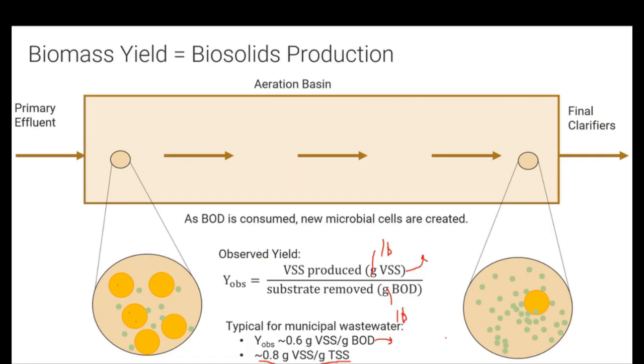One of the things you'll notice is that with shorter SRT, you get a higher volatile fraction. Longer SRT typically means you're going to have a lower ratio. So Mike, at 10 Mile, you have a higher SRT, so you're likely going to be lower than Cruise. Maybe you're in the 75 to 80% range. At some point, it kind of bottoms out. You don't go any lower. But this is your MLVSS to MLSS ratio.